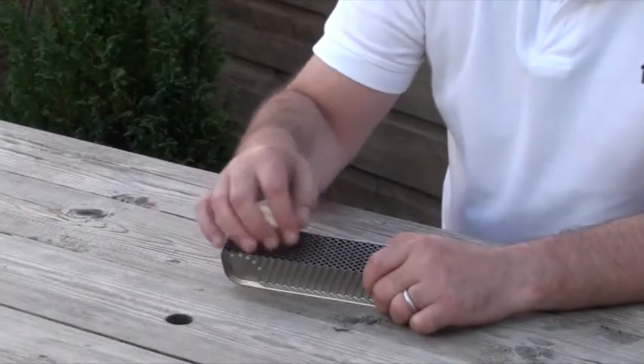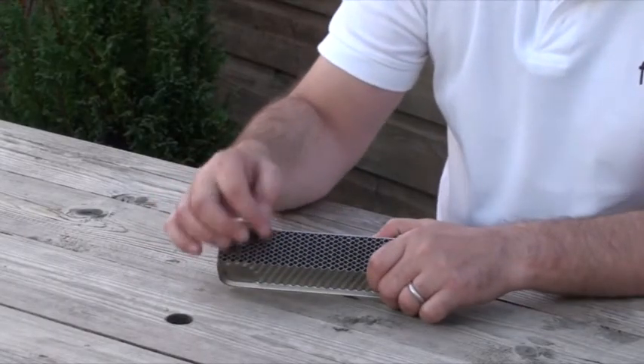As you can see in these little honeycomb pieces, little V's, the sediment just gathers and gathers and gathers over time. Now, if the layers underneath, say 1, 3, 5 and 7, are trying to heat 2, 4, 6 and 8 from below, what it's doing is first of all heating the sediment, and then that sediment is trying to heat your water. Obviously that doesn't sound very efficient, and it isn't.